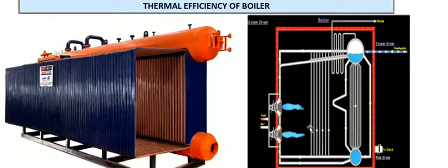At initial startup, the boiler will be purged for a certain time. After that, airflow will continue, and then with minimum flow, the fuel will be introduced with this ignition source. So we get proper combustion, and then flue gas will be generated, and indirect heat-up will happen in the tubes, and the water will become steam. Then the flue gas will exit through the preheaters or economizers, and then go to the chimney.